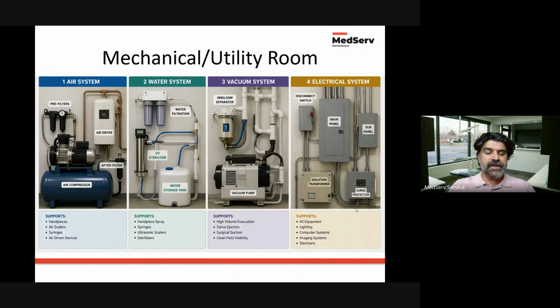So the compressed air is essentially the muscle, the flex of the dental tools. It's what supports the handpieces. That air pressure is what keeps those turbines turning and spinning the burs on those drills. It's what blows the air out of the syringes. It's also used for controlling the valves in the delivery unit. So when you have controls for adjusting position or adjusting speeds on certain handpieces, that's what the air is supporting or driving.